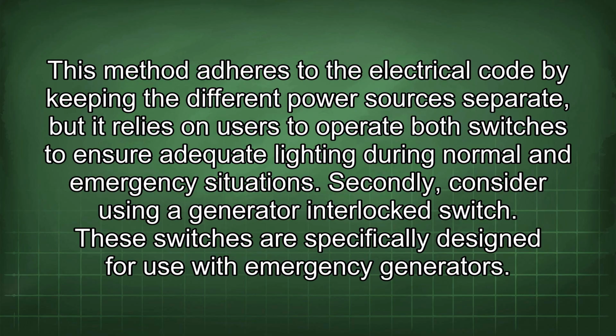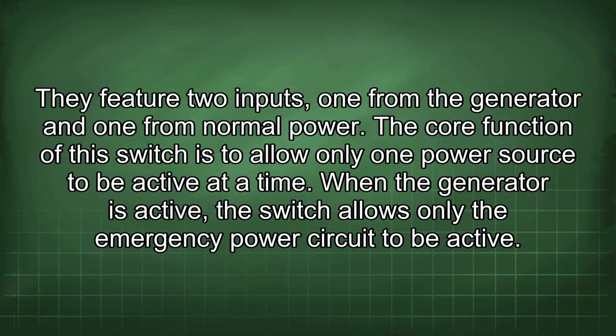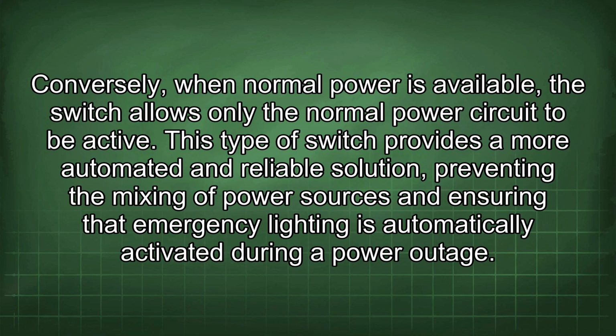Secondly, consider using a generator interlock switch. These switches are specifically designed for use with emergency generators. They feature two inputs, one from the generator and one from normal power. The core function of this switch is to allow only one power source to be active at a time. When the generator is active, the switch allows only the emergency power circuit to be active. Conversely, when normal power is available, the switch allows only the normal power circuit to be active. This type of switch provides a more automated and reliable solution, preventing the mixing of power sources and ensuring that emergency lighting is automatically activated during a power outage.